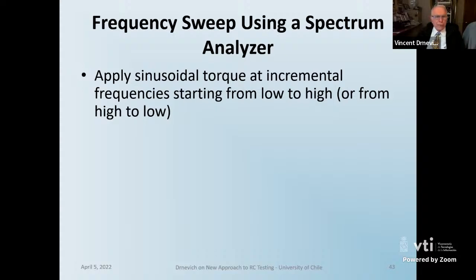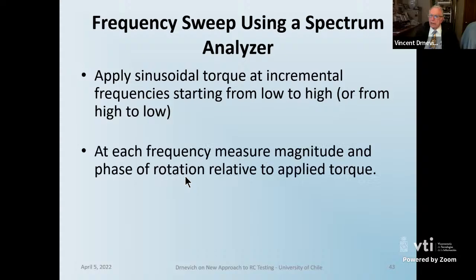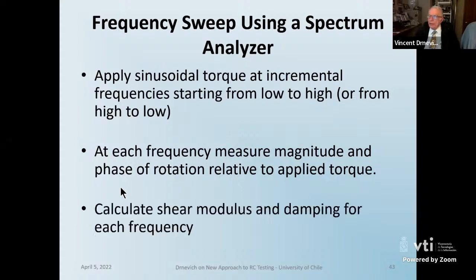And what about the frequency steps? Well, the frequency steps can be chosen. It could be as low as 0.01 hertz, which means you get a tremendous amount of data and very good definition to the curve. Or it could be 1 hertz if you want to, and that test runs very, very quickly. At each frequency, we measure the magnitude and phase of motion relative to the applied torque, and we calculate the shear modulus and damping for each frequency, as I've just explained to you previously.